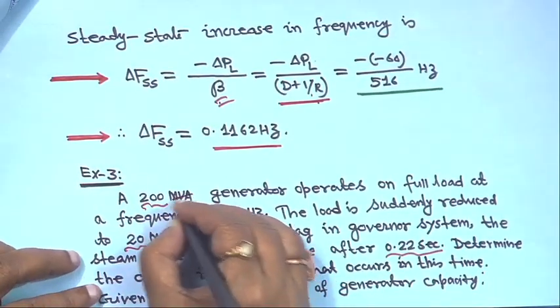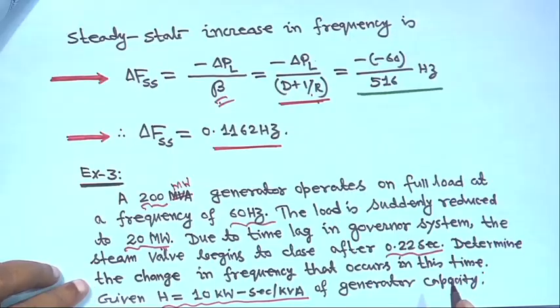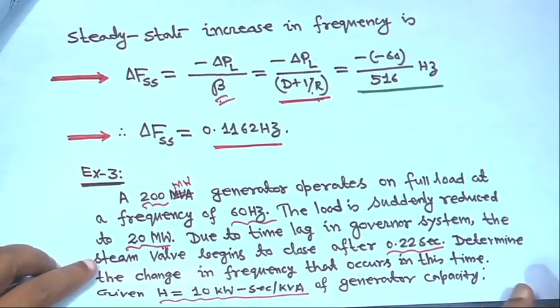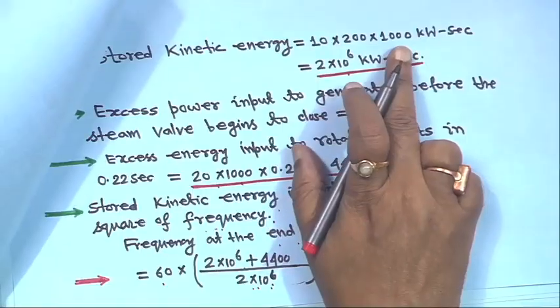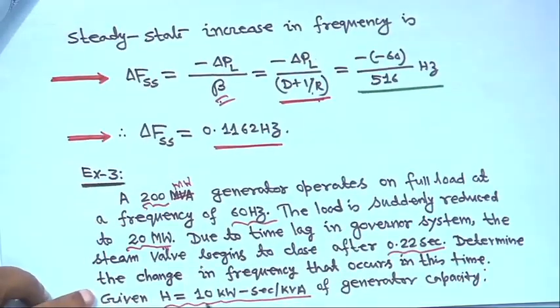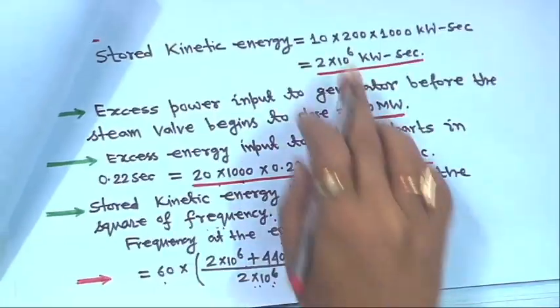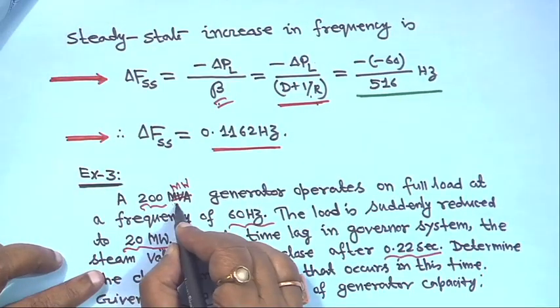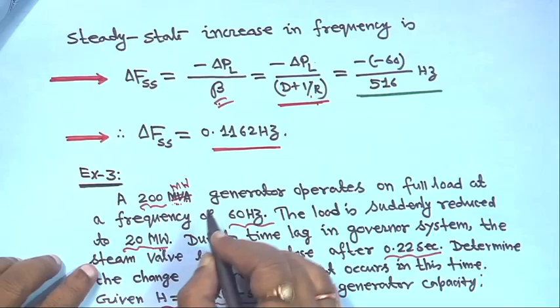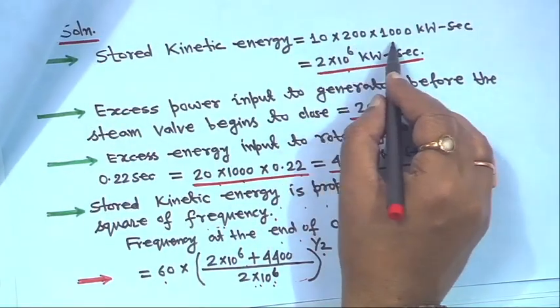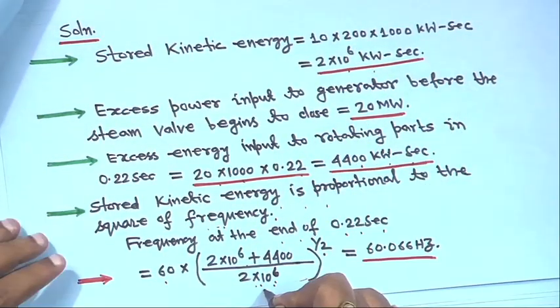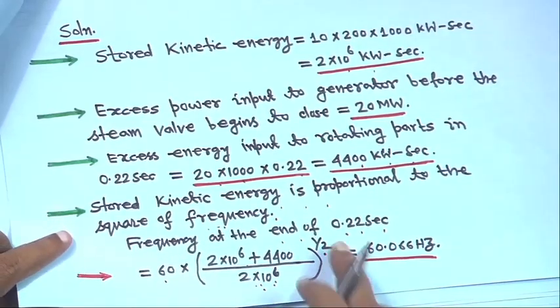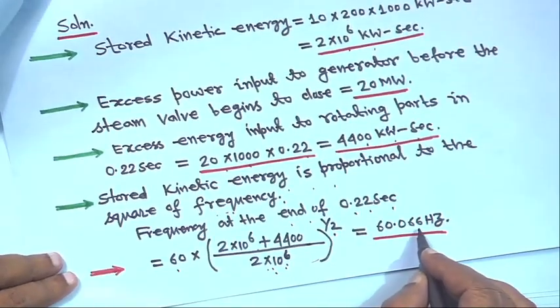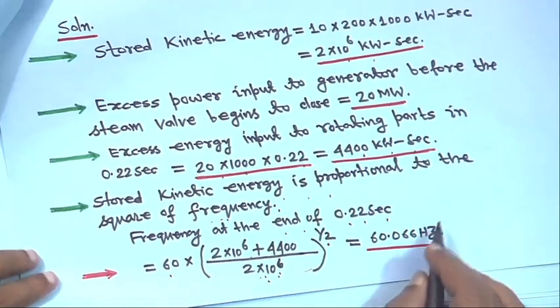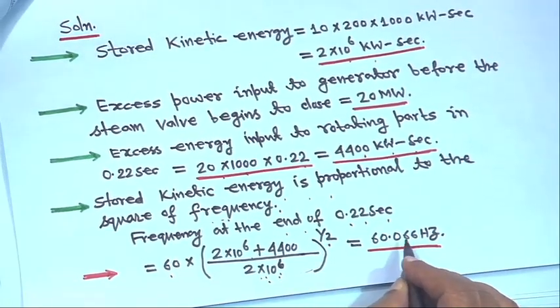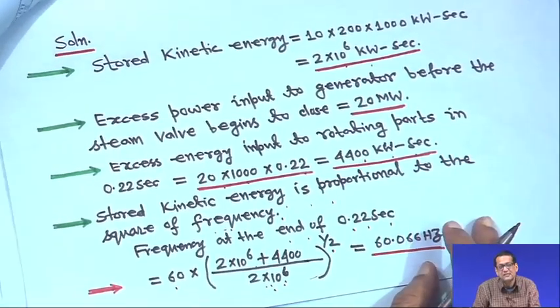There should not be confusion: you take a 200 megawatt generator, so that this is 200 into 1000 kilowatt, right, and H is given as 10 seconds. So it is PR into H, the rated capacity. So this is 200 megawatt, not MVA, so it is 10 into 200 into 1000 kilowatt second. This is a simple thing as far as this problem is concerned. So the frequency is increased by 0.066 hertz, slightly above your nominal frequency. We will see more problems. Let me finish this chapter.